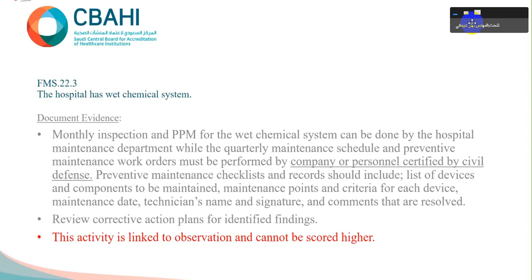So that's why once you visit the hospital, we have to ask the person responsible in the kitchen at what temperature, what degree, you have adjusted your trigger. As I remember, it was 80, 95, 110. So the people of the kitchen should identify the temperature or the degrees adjusted on the trigger or the sensor. And in case of fire, we have to interview all the staff in the kitchen on how to activate it, in case the system was not activated. So this is the manual valve. Again, PPM should be done by a company certified by civil defense. This is a sort of example.